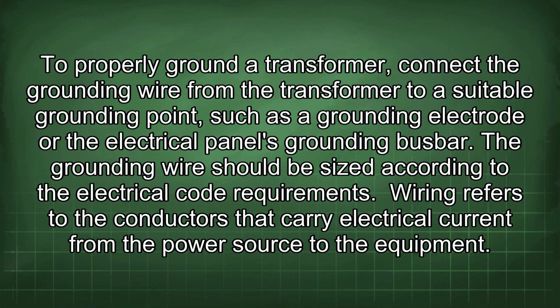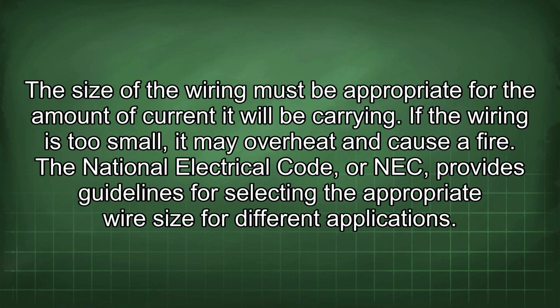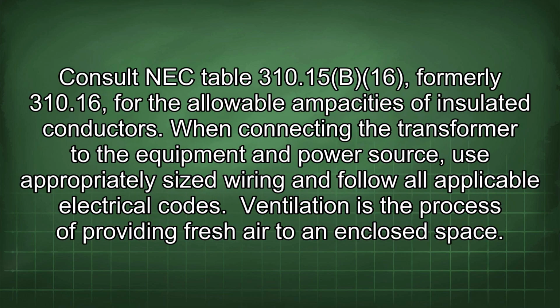Wiring refers to the conductors that carry electrical current from the power source to the equipment. The size of the wiring must be appropriate for the amount of current it will be carrying. If the wiring is too small, it may overheat and cause a fire. The National Electrical Code, or NEC, provides guidelines for selecting the appropriate wire size for different applications. Consult NEC Table 310.15(B)(16), formerly 310.16, for the allowable ampacities of insulated conductors. When connecting the transformer to the equipment and power source, use appropriately sized wiring and follow all applicable electrical codes.